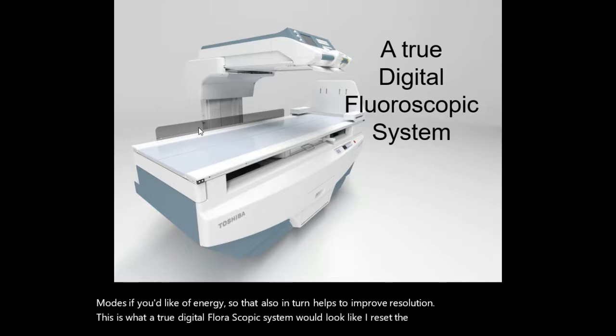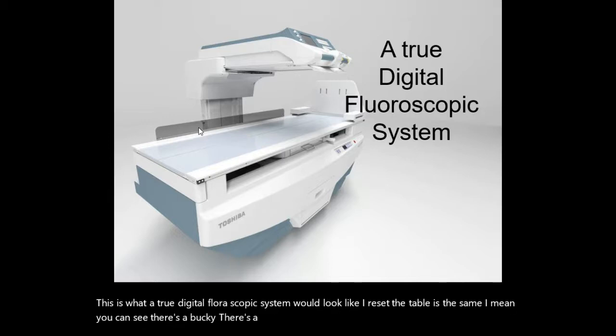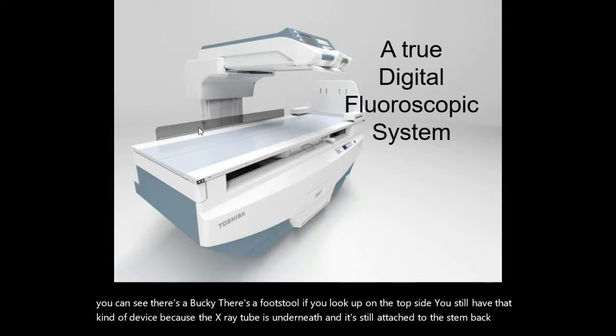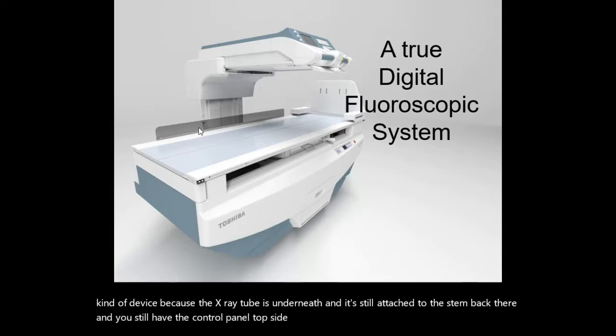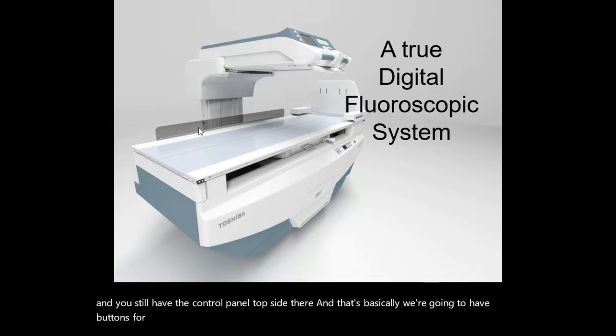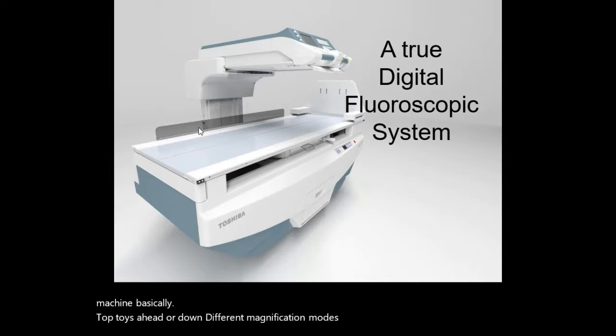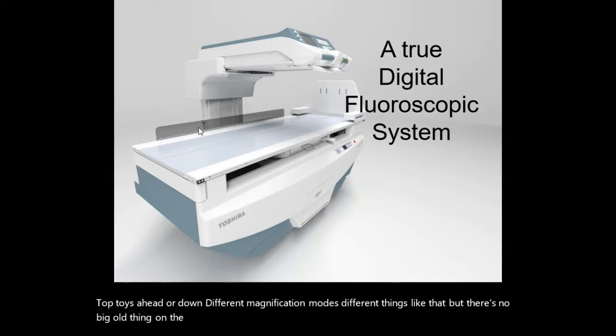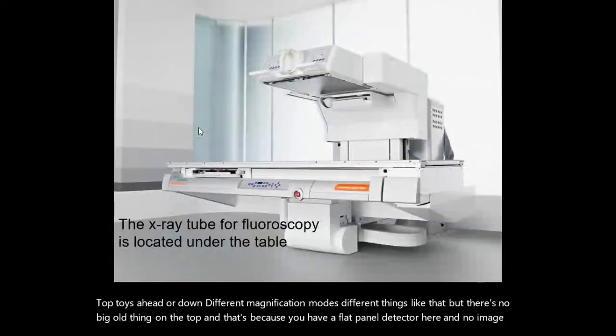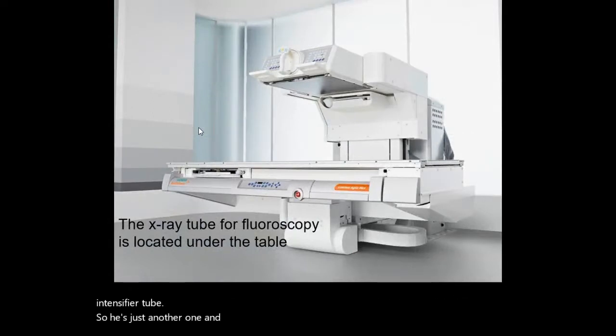Obviously, the table is the same. You can see there's a bucky, there's a footstool. If you look up on the top side, you still have a kind of C device because the X-ray tube is underneath and it's still attached to the stem back there. And you still have the control panel top side there. That's basically where you're going to have buttons for controlling whether the X-rays are on or off, whether you're going to move that machine up towards the head or down, different magnification modes, different things like that. But there's no big old thing on the top, and that's because you have a flat panel detector here and no image intensifier tube. Okay, so here's just another one. And this one actually can show you a little better that the X-ray tube is essentially right underneath.